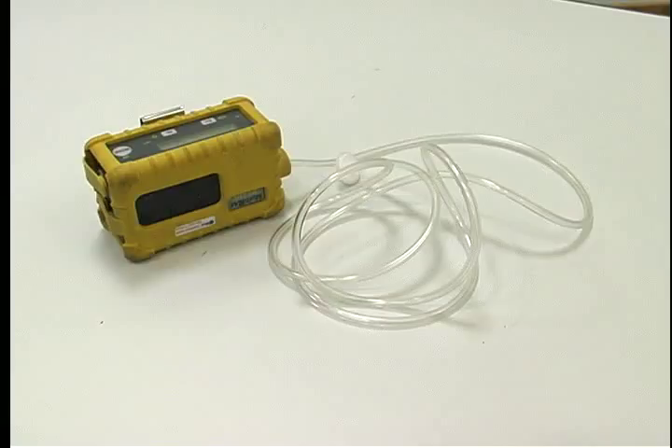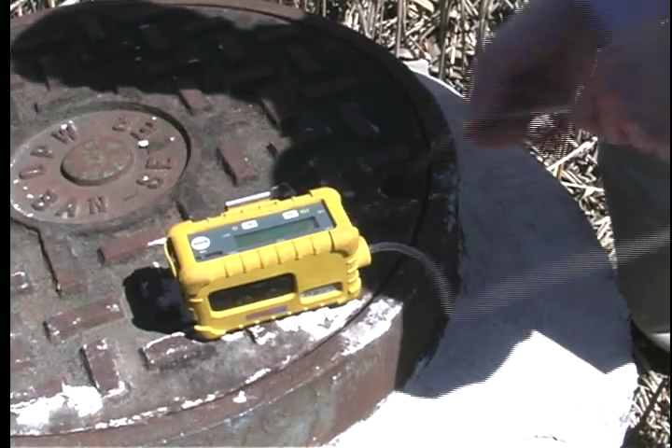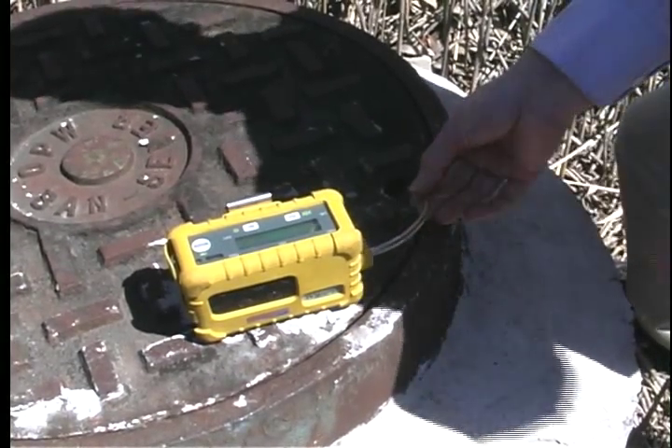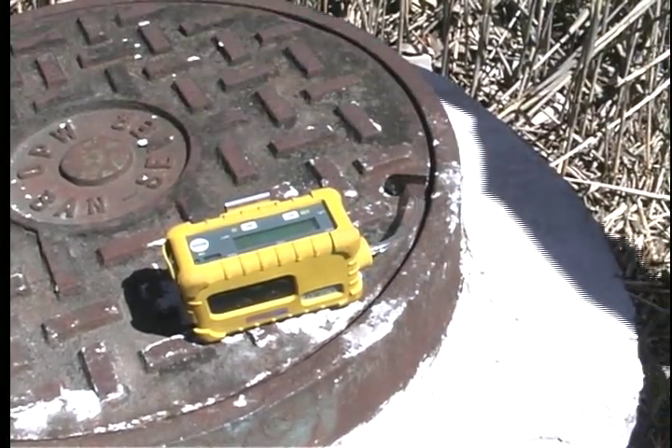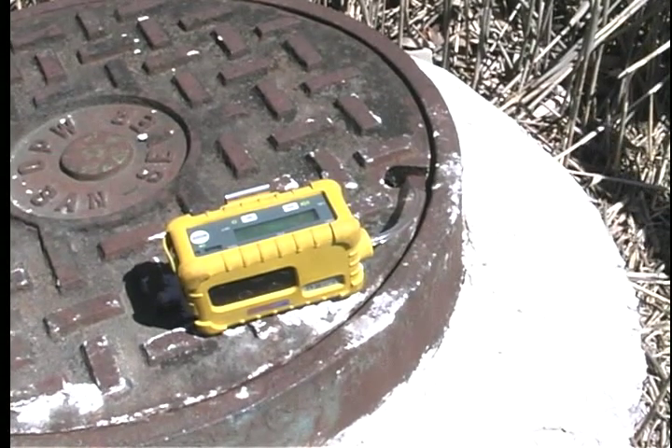To perform a remote survey, such as a manhole, you will need to have Galson send you the amount of Tygon tubing needed for the survey. The MultiRAE can sample remotely up to 15 to 20 feet with tubing attached. Setup is the same as personal or area surveys. After you attach the length of tubing to the unit, lower the tubing to where you would like to collect the data, then start the survey.